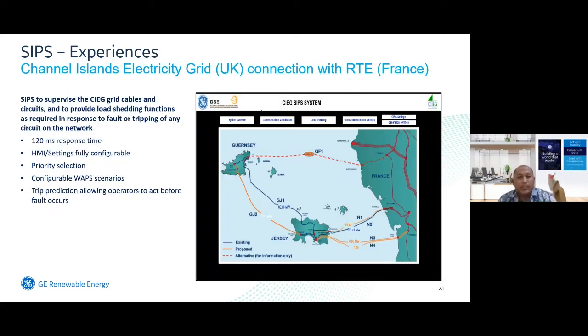So this is the second experience and reference that we have in Europe. This is related to the Channel Island electricity grid between the UK and the connection with RTE France. This SIPS has a function to supervise the CIEG grid cable and circuit and to provide load shedding function as required in response to a fault or tripping of any circuit on the network. The system can respond within 120 milliseconds. It also has an HMI and fully configurable settings, and has a function of priority selection, configurable scenarios, and also trip prediction. By having this trip prediction, it allows the operator to act before the fault occurs.